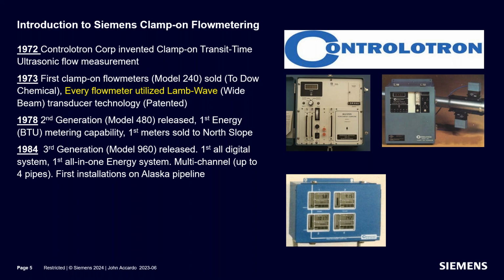We did introduce energy measurement in the 480 model, and in the 960 model we had an all-in-one energy meter, so you could have one device that measured flow and energy at the same time. And we did our first installations on the Alaska pipeline. We were utilized as a flow switch that performed a very critical operation to monitor flow. In the event that the flow dropped below a preset value, the flow meter would trigger an alarm that would drop a check valve and have it positioned just in case the flow in the pipe reversed. It would close the valve and prevent a reverse leak in the pipe. So they were deployed up and down the entire Alaska pipeline back in the mid to late 80s.